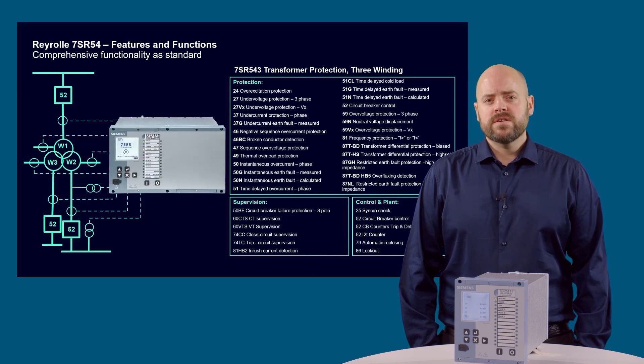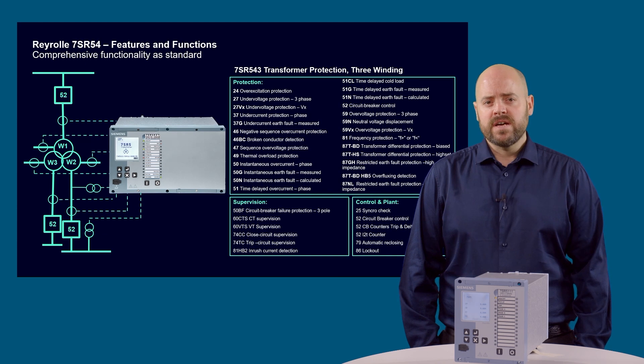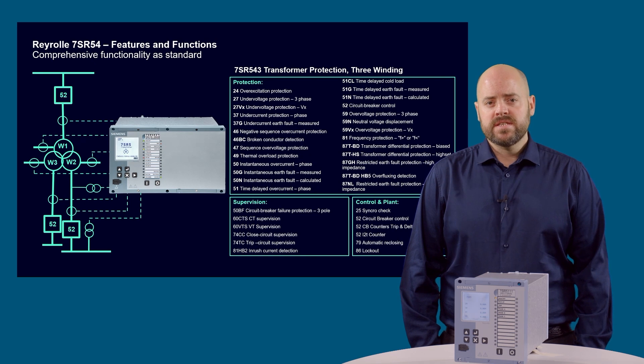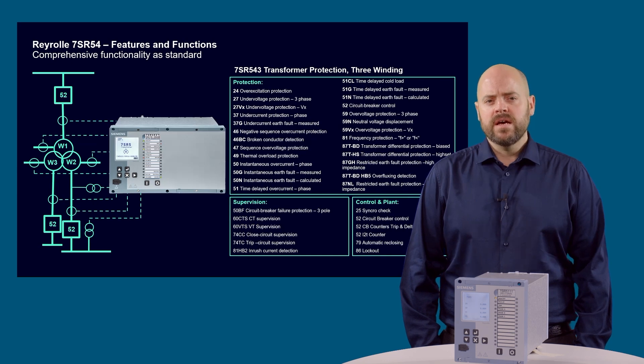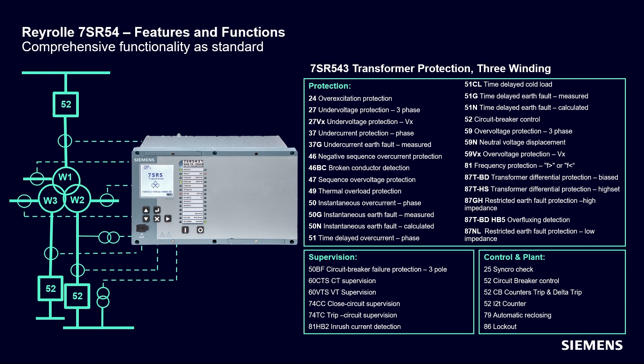The Reyrolle 7SR543 three-winding device provides comprehensive protection for three-winding transformers. The device also provides differential protection for auto-transformers. Its 12 CT inputs are suitable for connection to both 1A and 5A current transformer secondary windings and includes a core range of functions as standard. Additional 4 VT inputs are also optionally available.